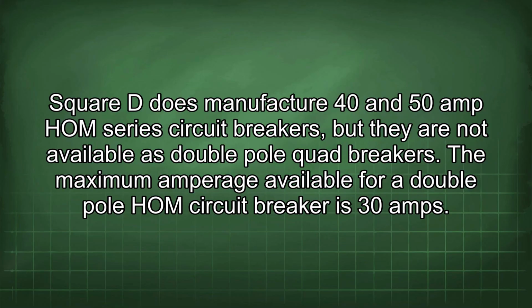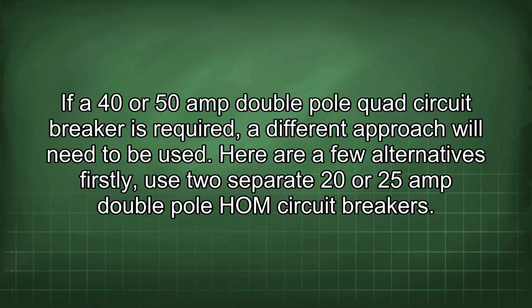Square D does manufacture 40 and 50 amp HOM series circuit breakers, but they are not available as double pole quad breakers. The maximum amperage available for a double pole HOM circuit breaker is 30 amps. If a 40 or 50 amp double pole quad circuit breaker is required, a different approach will need to be used. Here are a few alternatives.